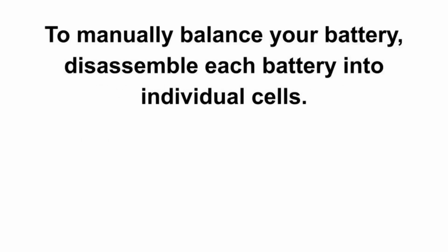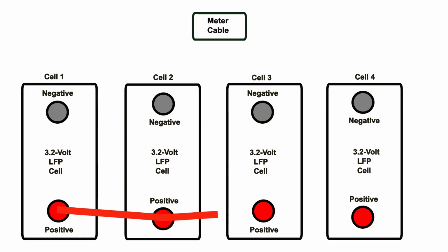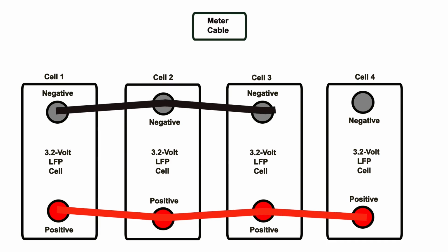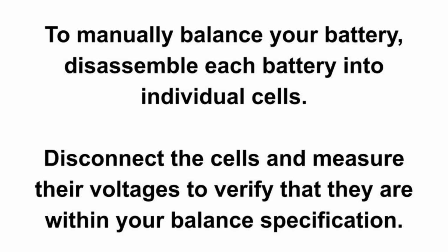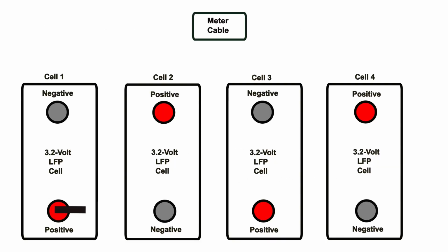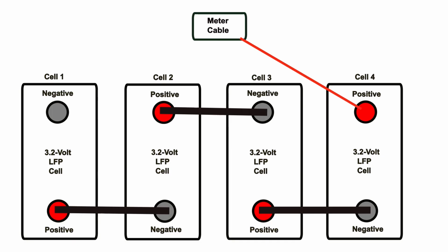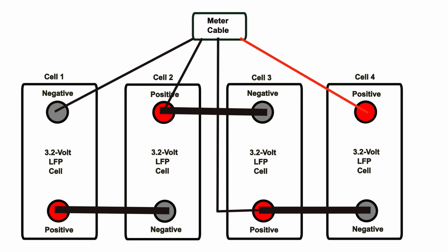To manually balance your battery, disassemble each battery into individual cells. Connect all of the cells in parallel and wait at least 48 hours until all of the cells are balanced to the same voltage. Disconnect the cells and measure their voltages to verify they are within your balance specification. Then put your battery back together in series, remembering to reconnect your BMS and any standalone meter cables.